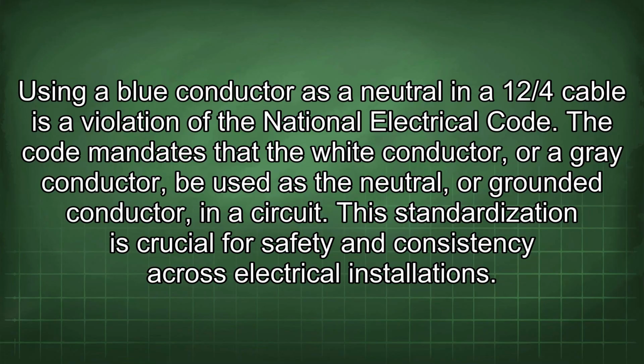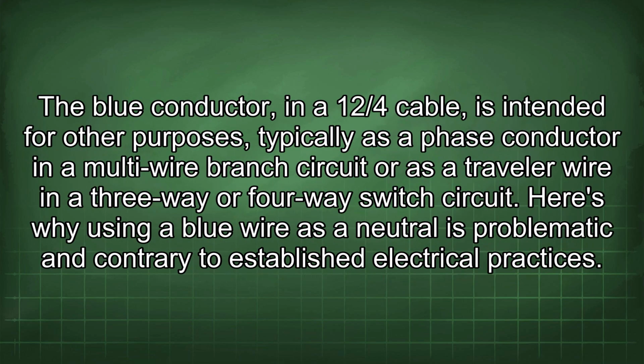Using a blue conductor as a neutral in a 12/4 cable is a violation of the National Electrical Code. The code mandates that the white conductor, or a grey conductor, be used as the neutral or grounded conductor in a circuit. This standardization is crucial for safety and consistency across electrical installations. The blue conductor in a 12/4 cable is intended for other purposes, typically as a phase conductor in a multi-wire branch circuit or as a traveler wire in a 3-way or 4-way switch circuit.